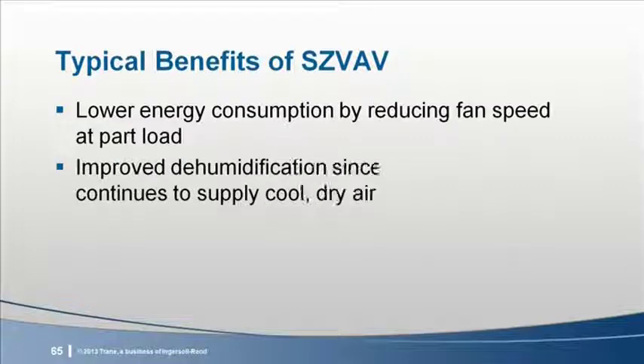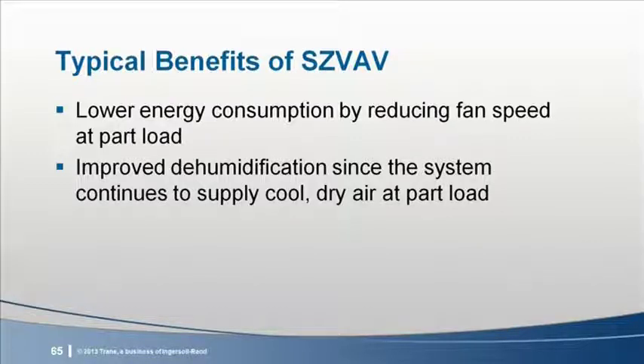The VAV system continues to deliver cool, dry air at part load conditions. This colder, drier discharge temperature has dehumidification benefits and energy consumption drawbacks, but the meter is on the building and the fan energy savings offset the additional compressor energy many times over. John's going to demonstrate with an example of part load dehumidification.